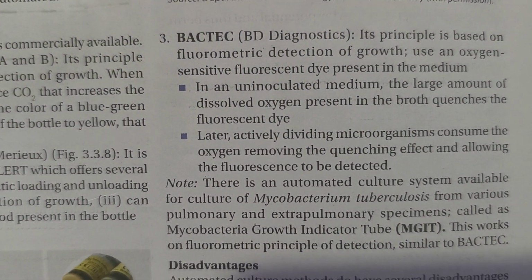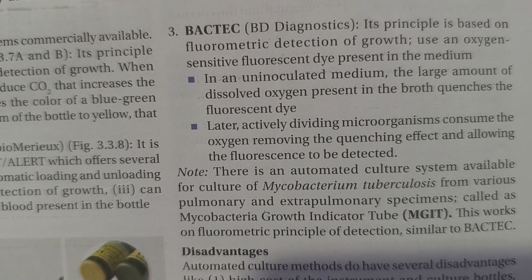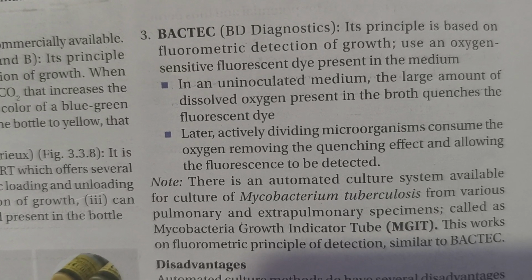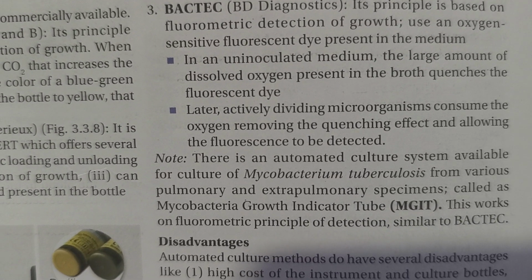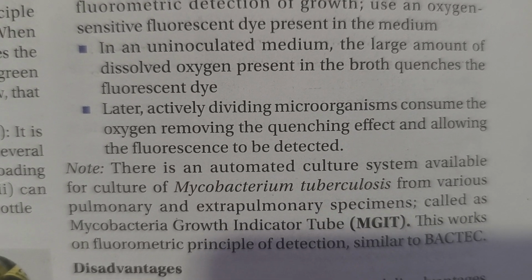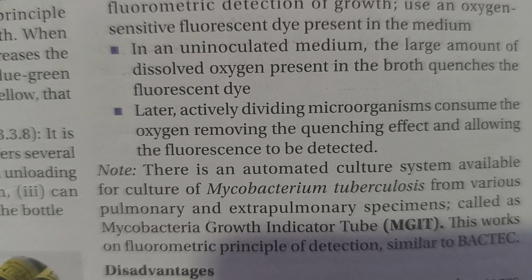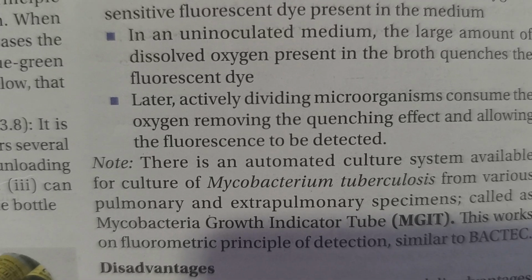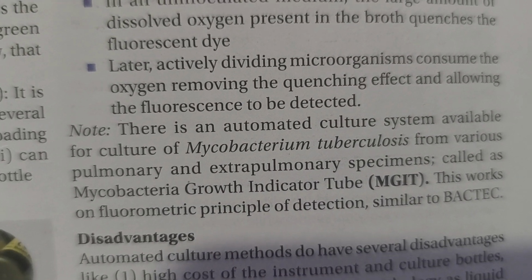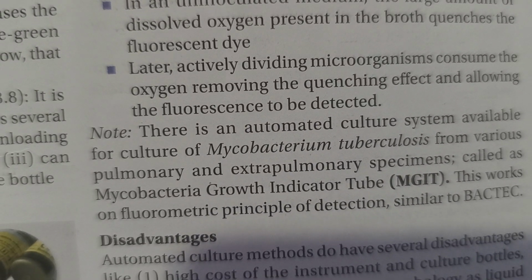Now let us see Bactec BD diagnostics. Its principle is based on fluorometric detection of growth, use of oxygen sensitive fluorescent dye present in the medium. In an uninoculated medium, the large amount of dissolved oxygen present in broth quenches the fluorescent dye.